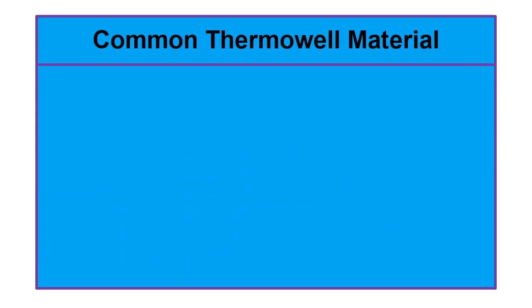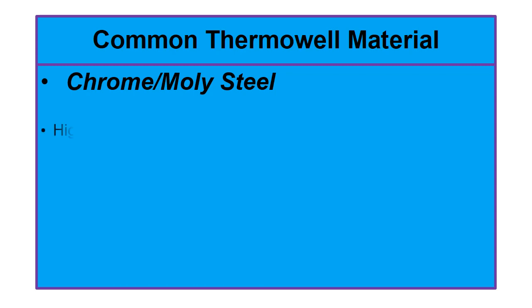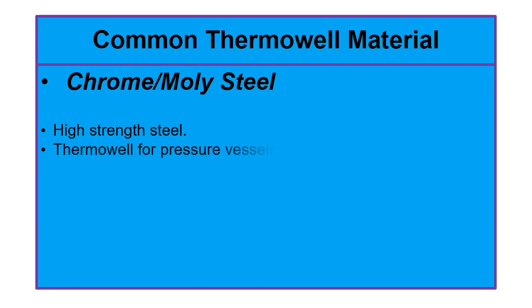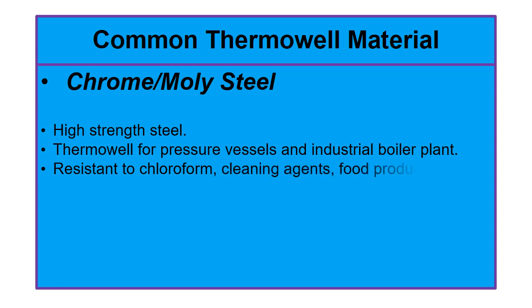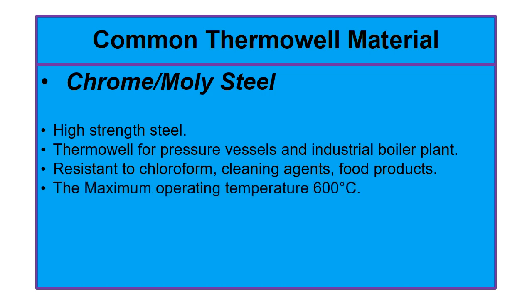The next material is chrome-moly steel. Chrome-molybdenum steel is a high strength steel. It can be used to make thermowells for pressure vessels and industrial boiler plants. Chrome-moly steel is resistant to chloroform, cleaning agents, food products, and carbon disulfide. The maximum operating temperature for chrome-moly steel is 600 degrees centigrade.